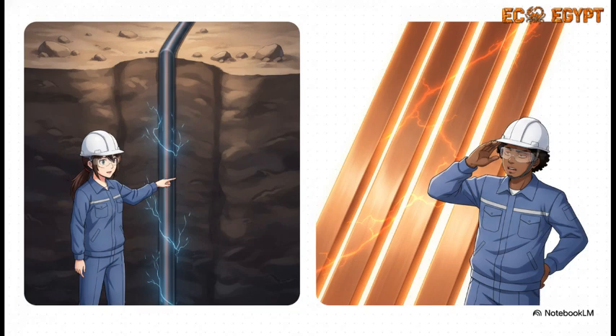But the LV cables connecting the transformer to the MDB, they aren't dealing with high voltage. They're dealing with massively high current. We're talking sometimes over 6,000 amps. So instead of distance, LV connections need massively thick parallel setups, like 4 500 square millimeter copper cables or rigid bus ducts, literally just to carry that load without melting into a puddle.